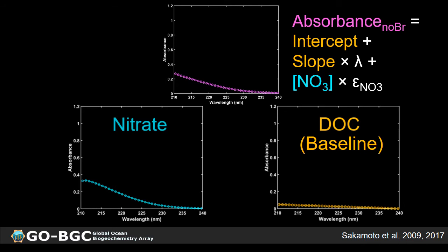And I should mention right now that the DOC component also takes care of any shifts in the baseline or the performance of the lamp itself. So for example, if the lamp intensity changes due to temperature changes or aging, the DOC component largely takes care of that, because these shifts in the lamp intensity manifest as a change in the intercept or a constant offset in the absorbance. So the intercept will basically take care of such drift.